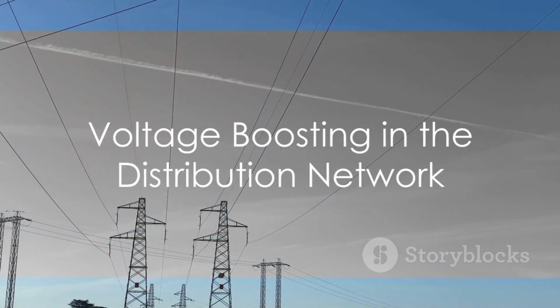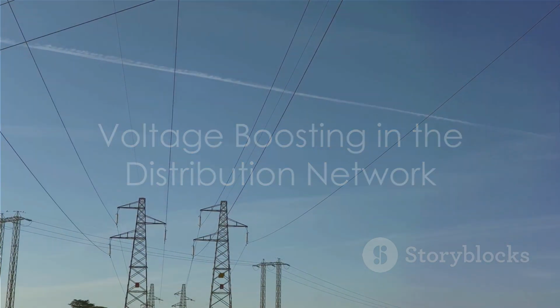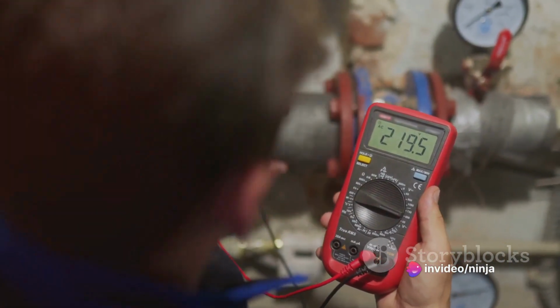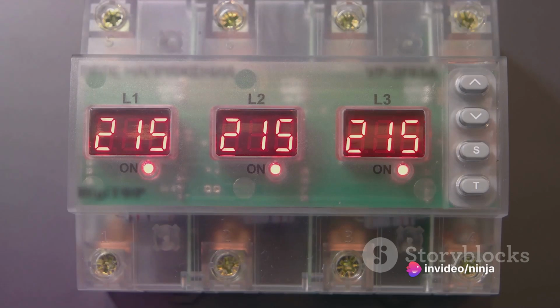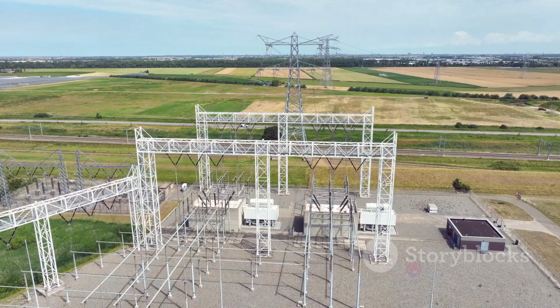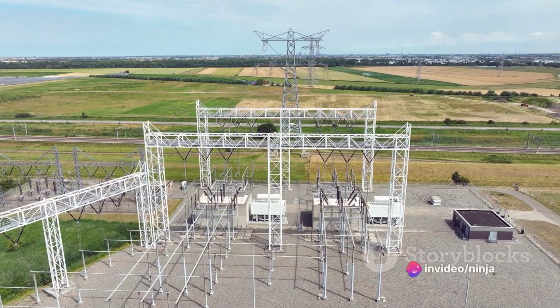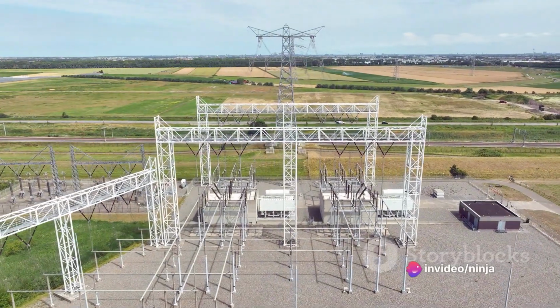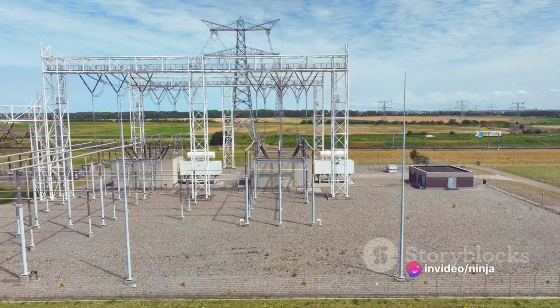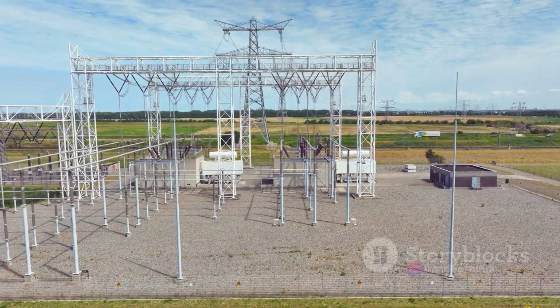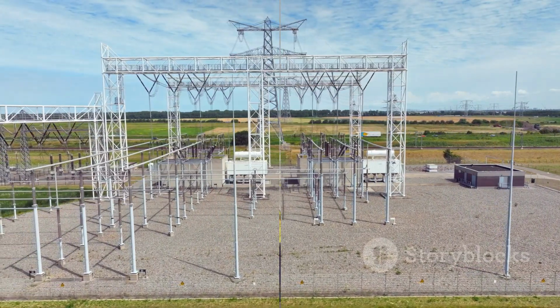Now imagine a long feeder stretching away from the main substation. The further away you go, the lower the voltage on the medium voltage feeder becomes. To counteract this, different turns ratios are used in medium voltage to low voltage transformers, sometimes referred to as offload tap changers. The turns ratio is smaller at the end of the feeder, which boosts the voltage on the secondary side. This technique can boost the voltage in the distribution network by up to 5%.